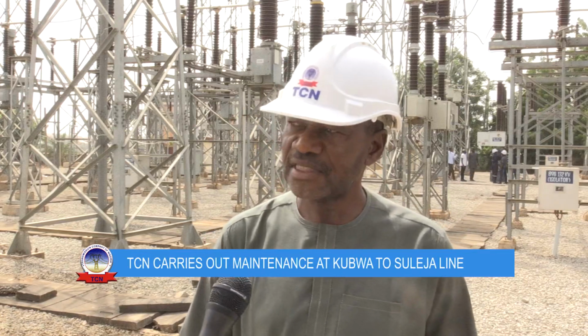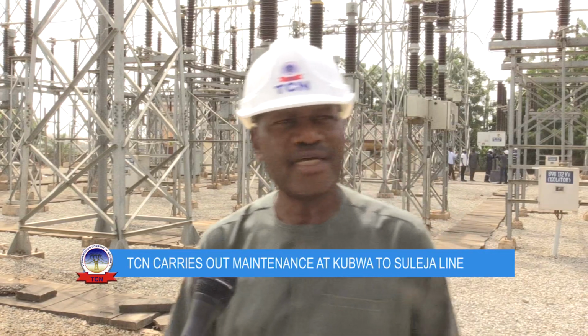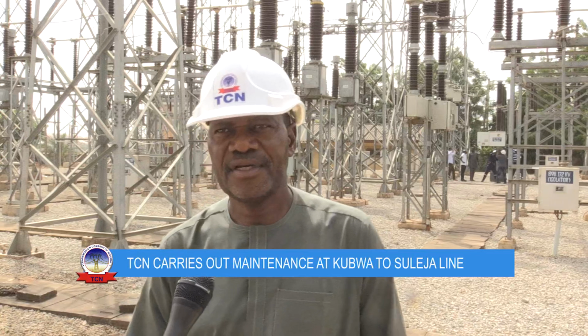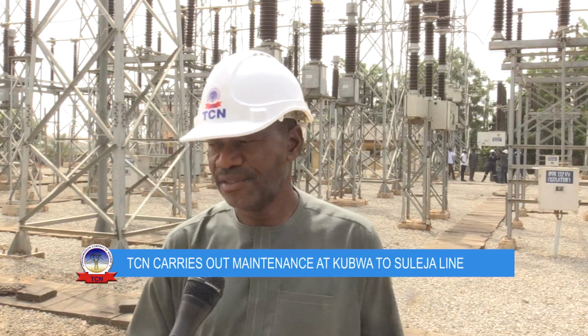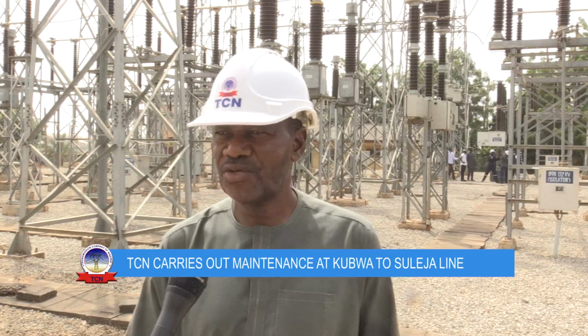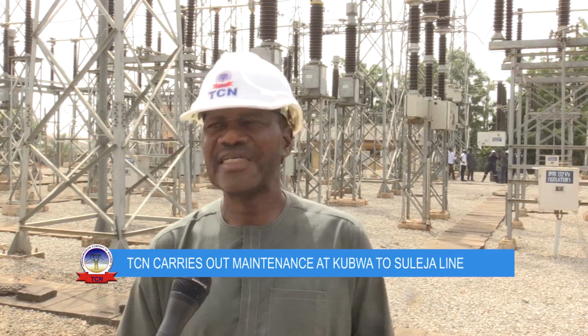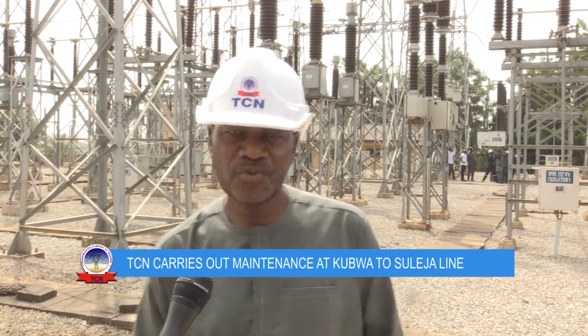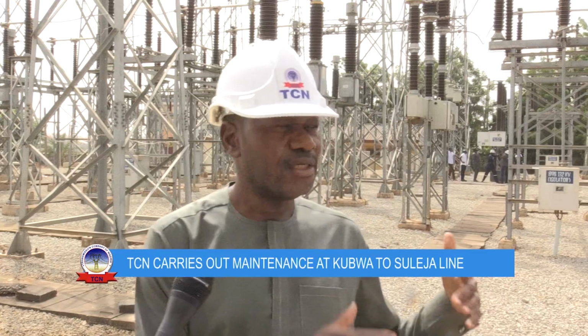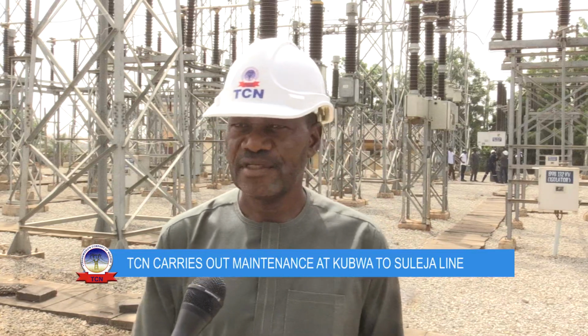So we took the advantage and tested the transformer. We realized the insulation level had gone down so seriously that we couldn't even attempt to bring the transformer back. That's why we went for serious filtration, and afterwards we tried again.